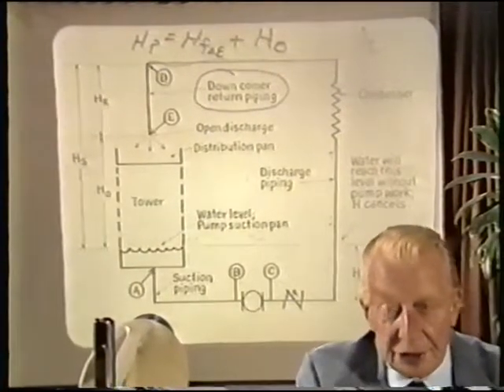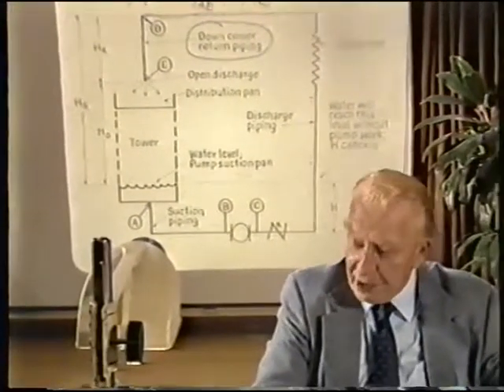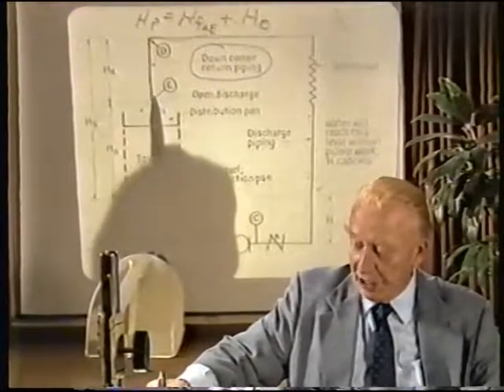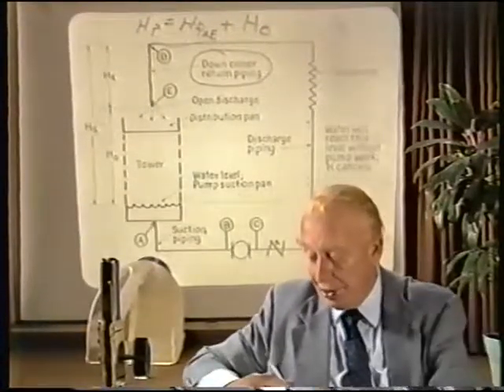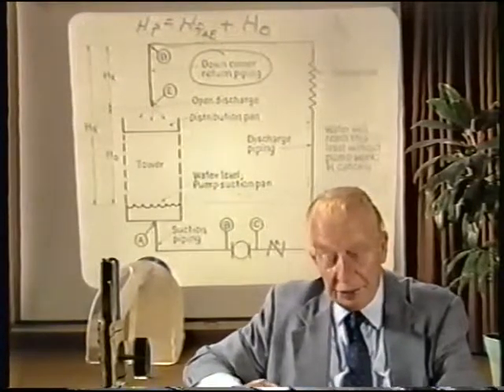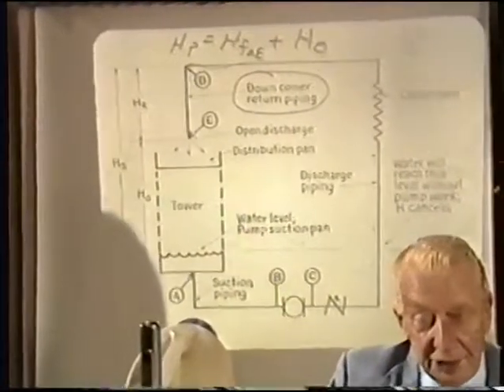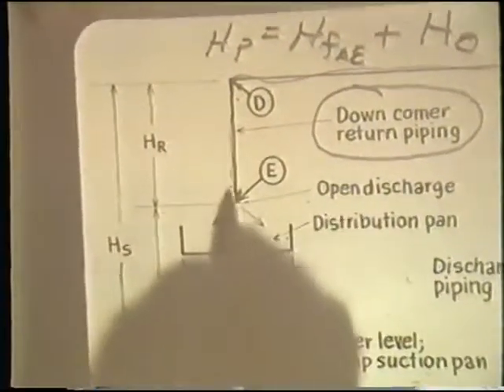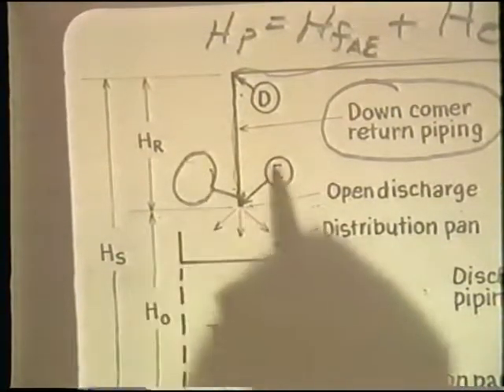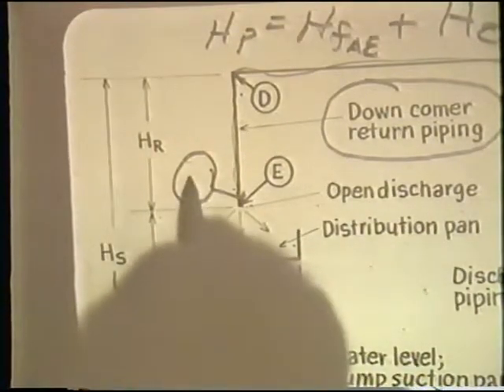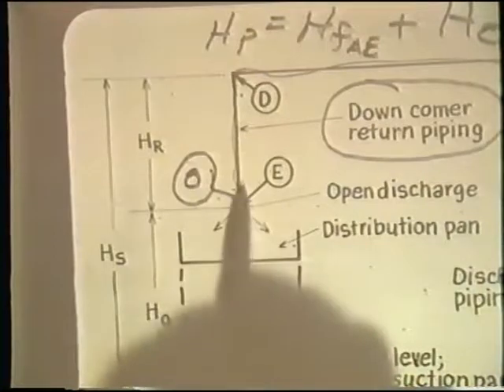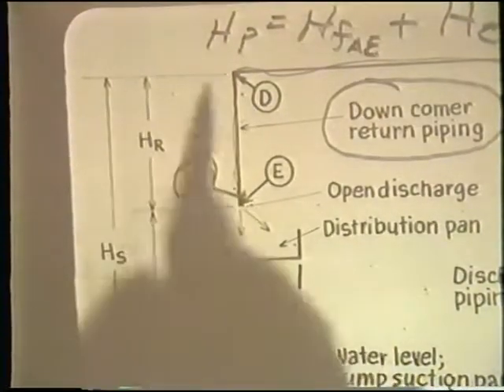And this is the generalized consideration for pump selection, but is based on a full pipe drawing a siphon return as from E to D. Now, so long as the downcomer return pipe is reasonably short in length, we can establish that siphon return. On the other hand, it must be remembered that the pressure available at the discharge of the conventional piping system has zero atmospheric pressure. And the static height H sub R, because this is above the discharge point, will be operating at a pressure which is less than atmospheric.